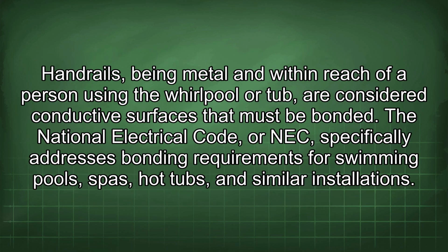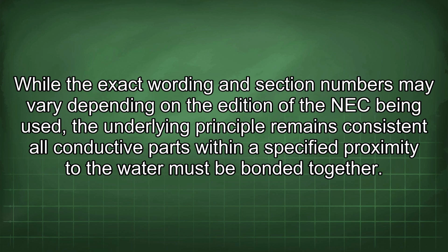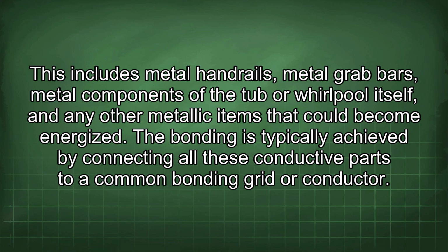Handrails, being metal and within reach of a person using the whirlpool or tub, are considered conductive surfaces that must be bonded. The National Electrical Code, or NEC, specifically addresses bonding requirements for swimming pools, spas, hot tubs, and similar installations. While the exact wording and section numbers may vary depending on the edition of the NEC being used, the underlying principle remains consistent. All conductive parts within a specified proximity to the water must be bonded together.